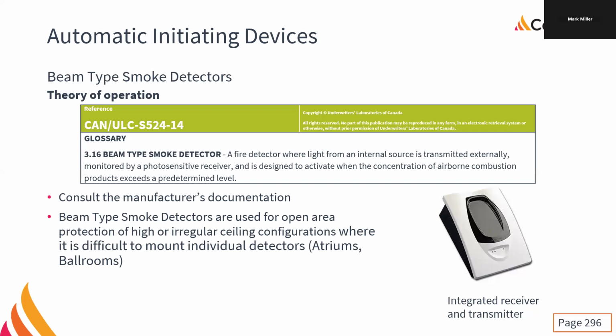At the same time, though, if you're putting these into somewhere like a gymnasium, you need to use a really, really good cage because it's just a target begging to be bombarded by projectiles. They're great for very high areas, large open areas, or irregular ceiling configurations. So we've got all sorts of architectural wonderments like in atriums and stuff like that, ballrooms. Beam detectors are absolutely the way to go.